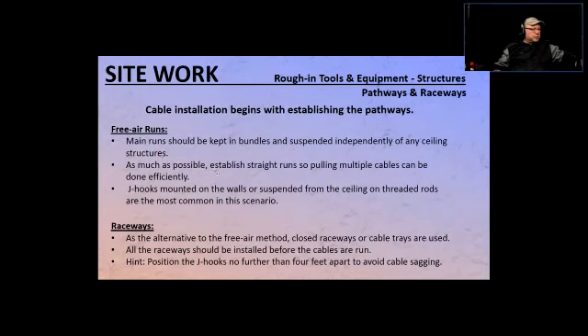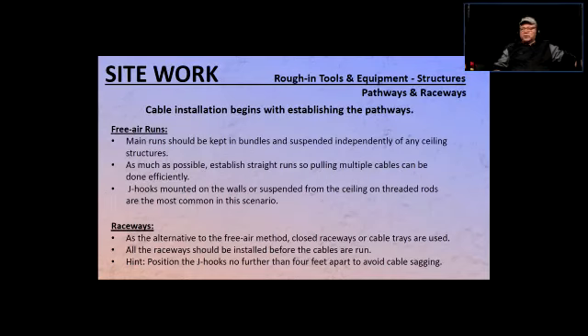As much as possible, establish straight runs so that pulling multiple cables can be done efficiently. If you establish a straight path and have multiple runs to perform, the straighter the path is, the better it's going to be for you. When you strain pulling the wires, the job gets slower and there is a chance that existing wires in the run might get damaged due to friction.